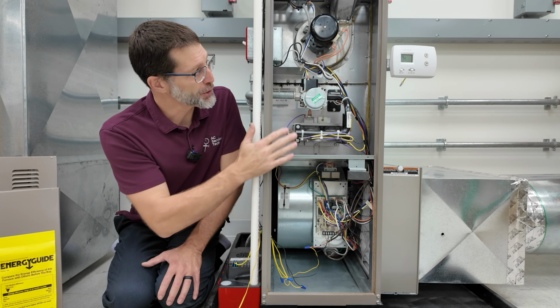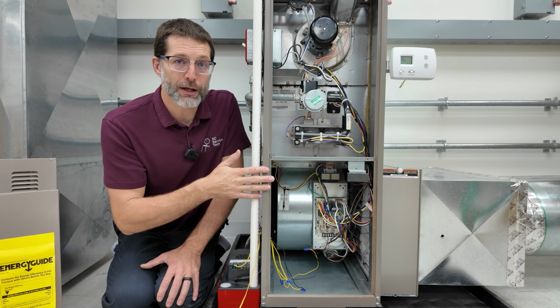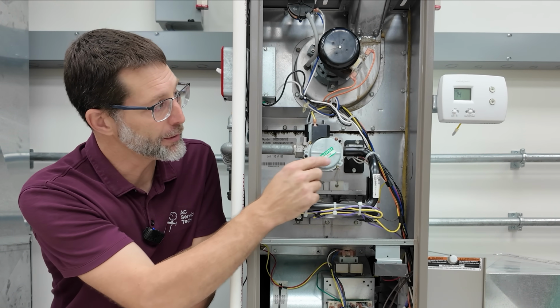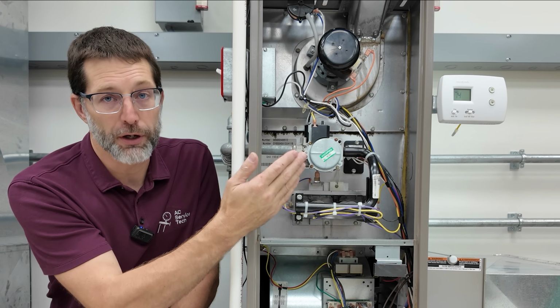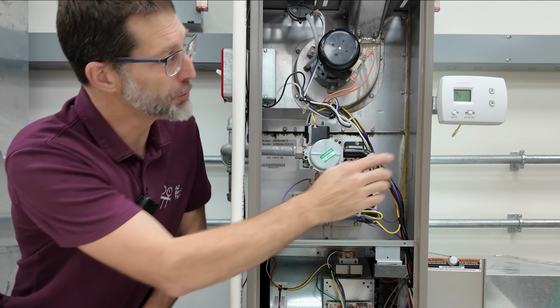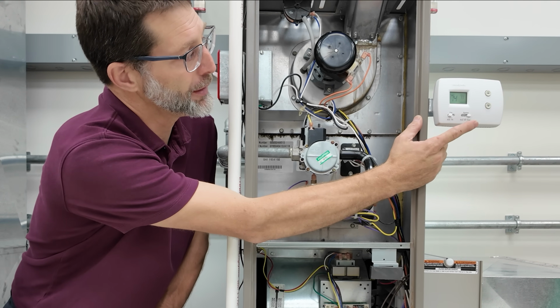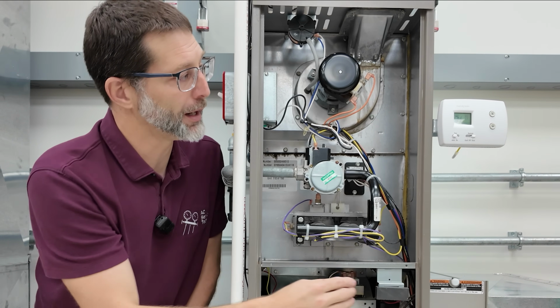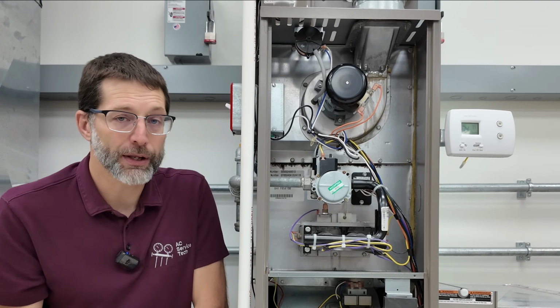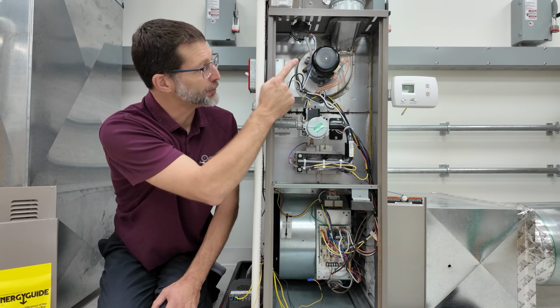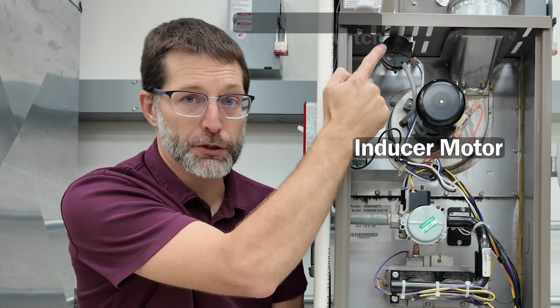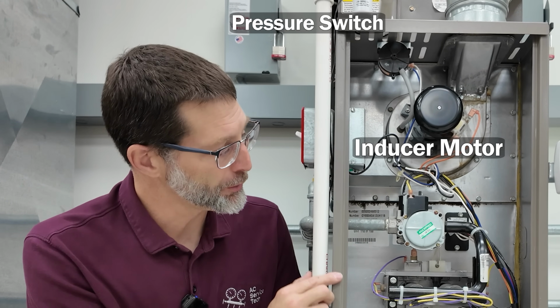What I'm going to do is show you the sequence of operation. What's happening inside this thermostat is the red and the white wires are touching. That's the R and the W wires when you turn heat on. So we're going to turn heat on, making sure it's set to a high enough temperature. The very first thing that turns on is this inducer motor. This pressure switch is confirming that the inducer motor is working.